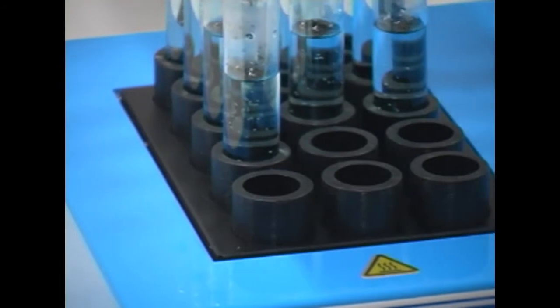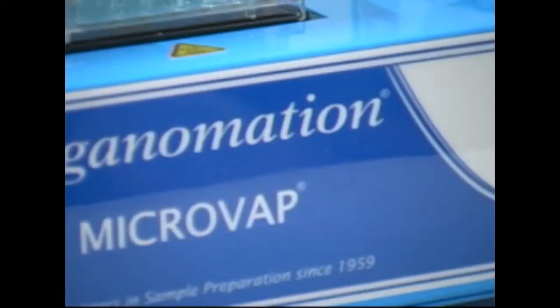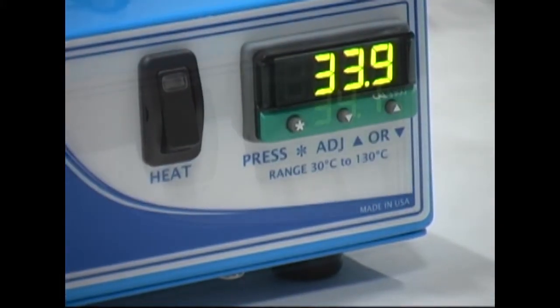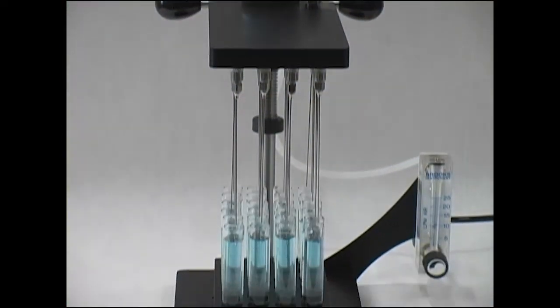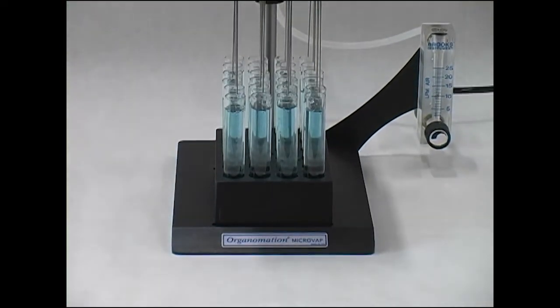This instrument comes with a heated aluminum dry block which provides reliable uniform heat up to 130 degrees Celsius. A version without heat is available for evaporations that will be performed at ambient temperatures.